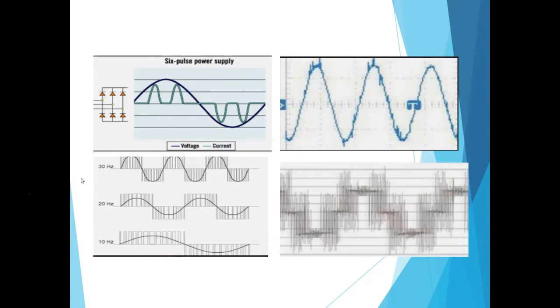And we have various suppliers that provide input filters and output filters, especially on submersible pump applications. You've got a deep well, maybe down 200-300 feet where the motor is, so you get a lot of resonance. It can distort the wire if it's gone unchecked, and then over time you're pulling the pump out prematurely, and that's a no-no and very expensive. And then we have various manufacturers that we know of that have great motors with special spike resistant wire, built in Germany, and have special types of film on them that also overcome some of those issues.